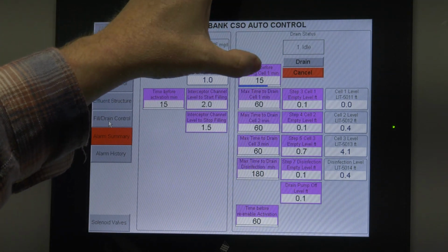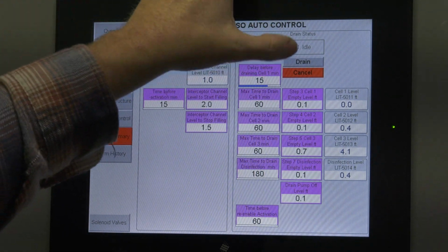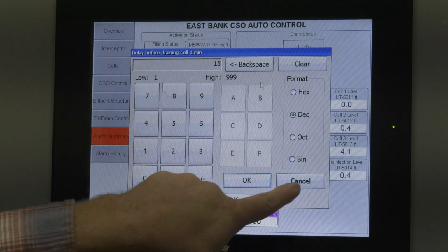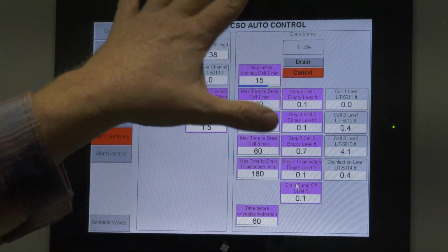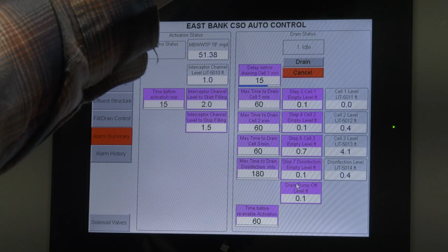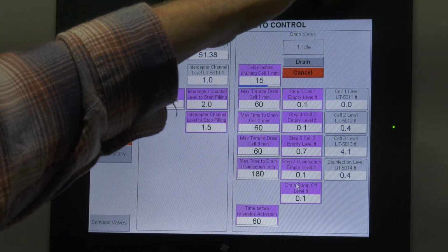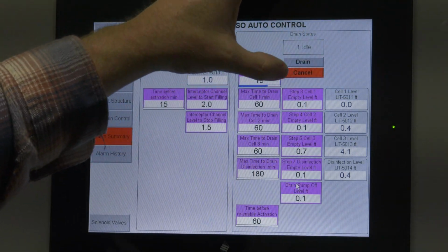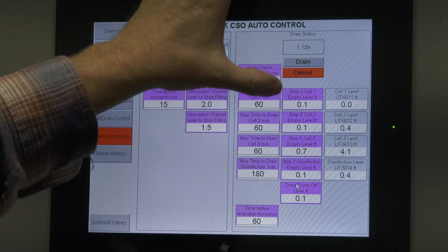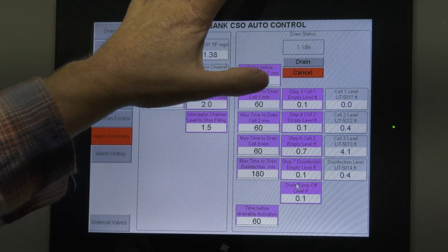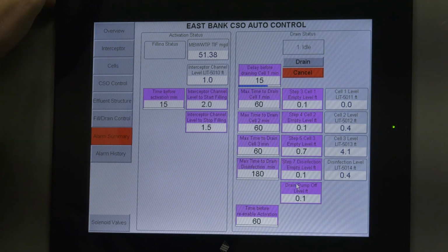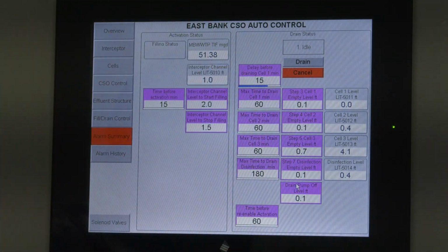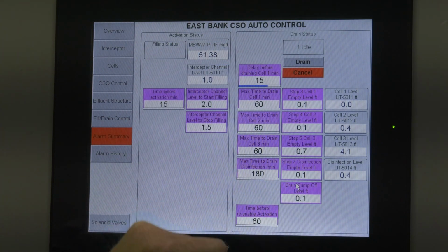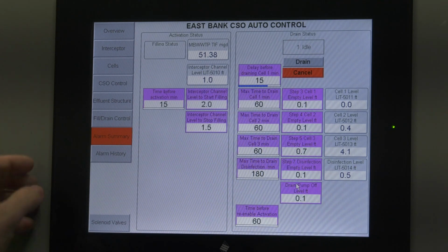It'll wait 15 minutes once you hit the drain cycle. Operator adjustable. All the purple or pink is operator adjustable. It'll wait till the level in cell 1 is less than 0.1 or 60 minutes, and then it moves to cell 2, cell 3, cell 4. And you've got a time before you can reactivate the drain sequence. It's currently set at 60 minutes.